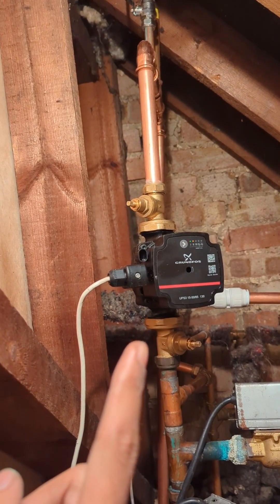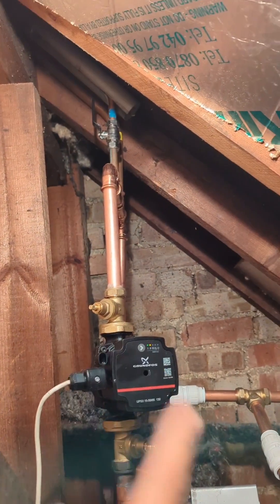Turned it on — and remember this tee wasn't getting hot — it's baking now, straight away within seconds. And that pump, yes, it was pulsing because it was obviously running dry; there wasn't enough water in the system. But now we are good.